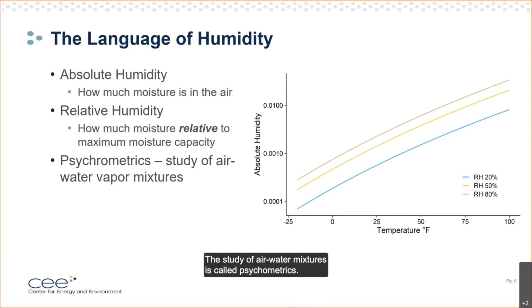The study of air-water mixtures is called psychrometrics. Mechanical engineers spend a lot of time in school looking at complex charts to understand these air-to-water mixtures, since they're important for HVAC design. But I want to set that aside and just draw your attention to two principles using this chart, which shows absolute humidity — again, think of it as a percentage, ranging from close to 0 to maybe 1%. For lines of fixed relative humidity, shown here as three examples, absolute humidity changes as a function of temperature. In short, warm air holds more moisture than cold air.